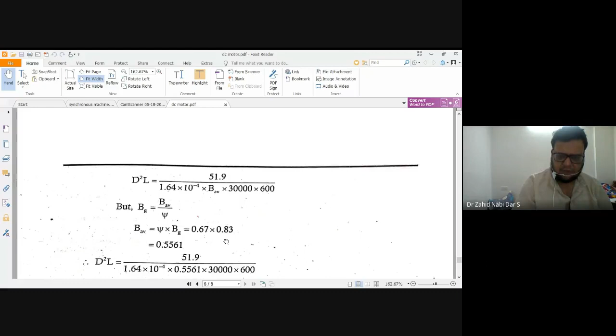Remember, that is your maximum value. Your average value is 0.67 into 0.83. So this is the BAV value, not this; 0.83 is the maximum value. The average value is pole arc to pole pitch. This problem we have done yesterday also. Once you multiply this value, you get D square L as 0.0316 meter cube.